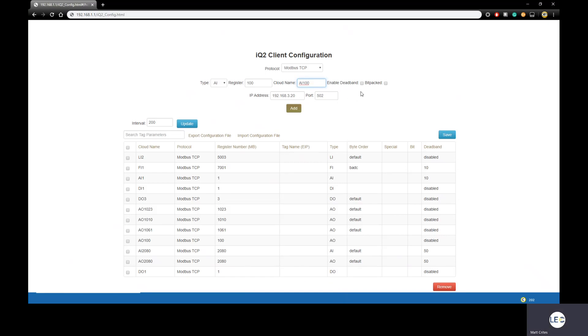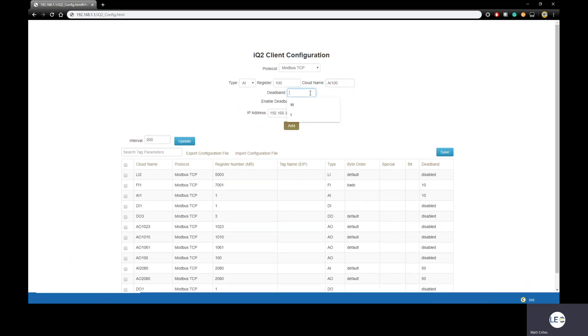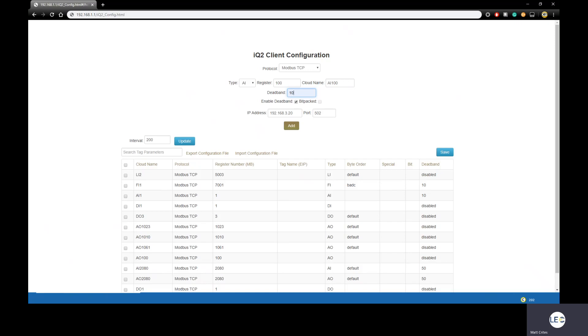Next, do we need a deadband? So if a register value changes by at least this entered value, send that update to IQ2. If I put a checkmark into the Enable Deadband checkbox, the deadband field appears, and I'll say if my value changes by more than 10 in either direction, so plus or minus 10 points, go ahead and send that update up to IQ2. Next, we have to enter an IP address. The IP address here is the Ethernet IP of the device the CloudGate is polling. It doesn't matter if it's a PLC, an RTU, whatever we are connected to via the Ethernet port on the front of the CloudGate, what is that connected device's IP address? Enter it into the IP address field, followed by the port number that that device is listening on. Since we're using Modbus TCP, I'm going to leave that port at 502.